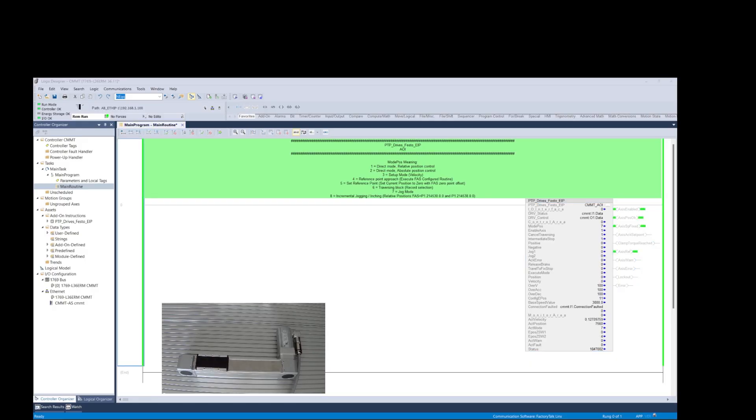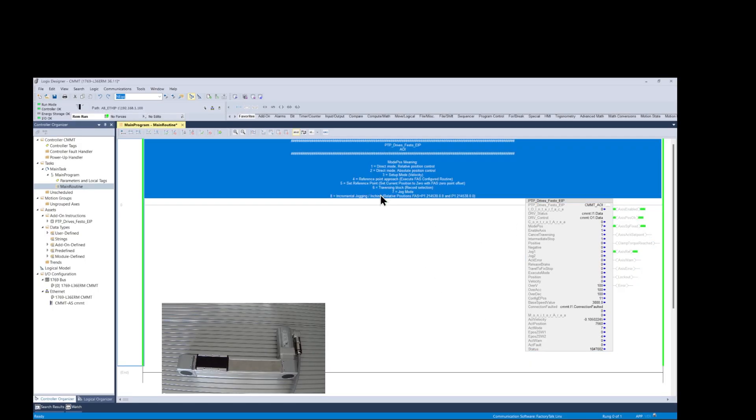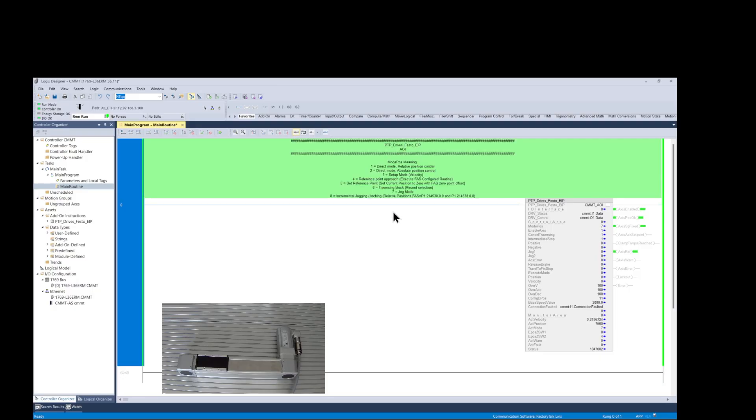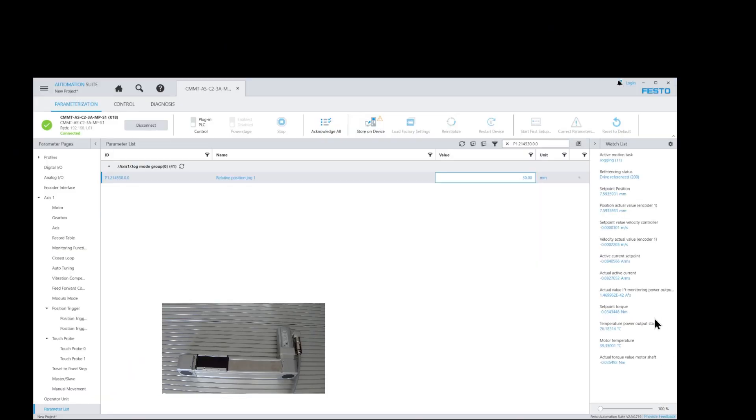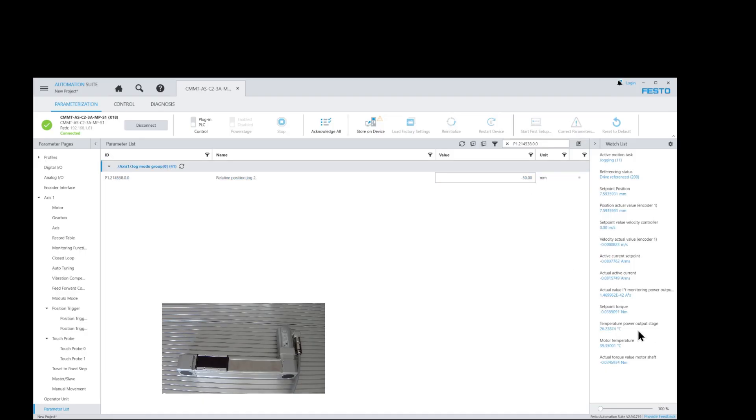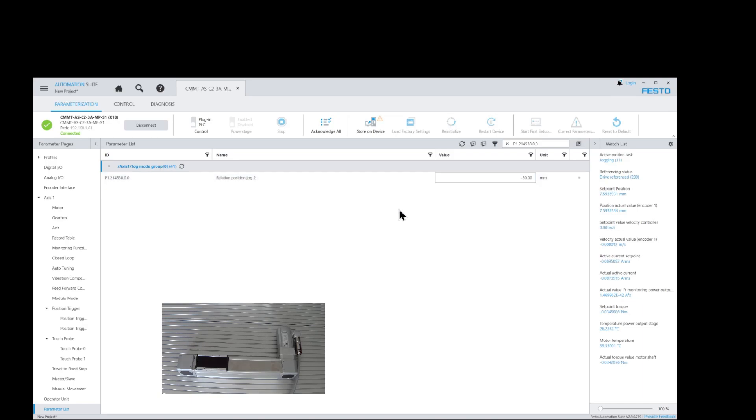The last mode is the incremental jogging. It works the same way as mode 7, which is typical jogging. But in incremental jogging mode 8, the jog is a predefined incremental move that is also set inside the FAS software. For positive jog 1, we use the relative position jog 1 parameter. And for negative jog 2, we use the relative position jog 2 parameter. In our case, the value is set to 30 mm per jog action.